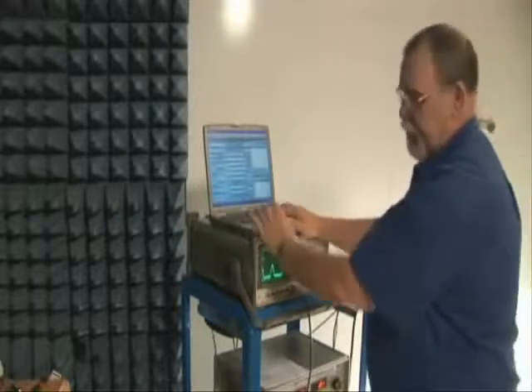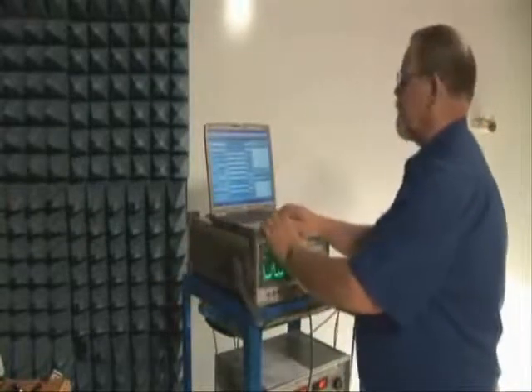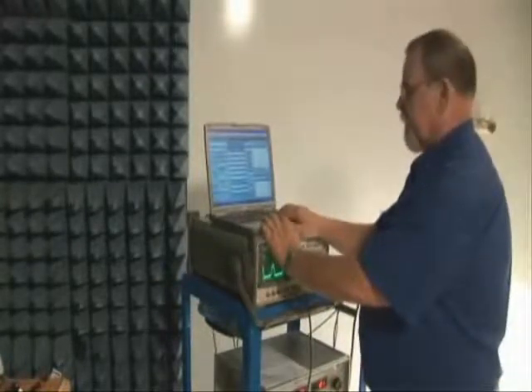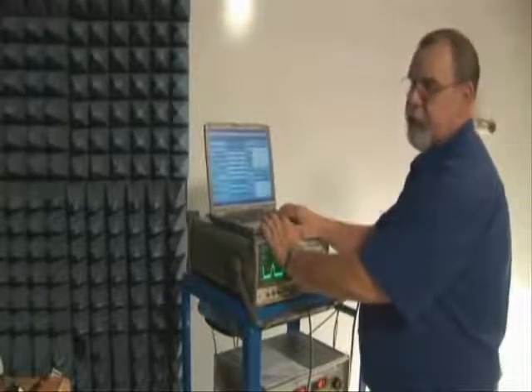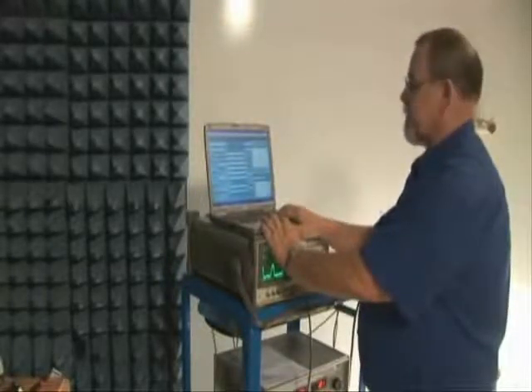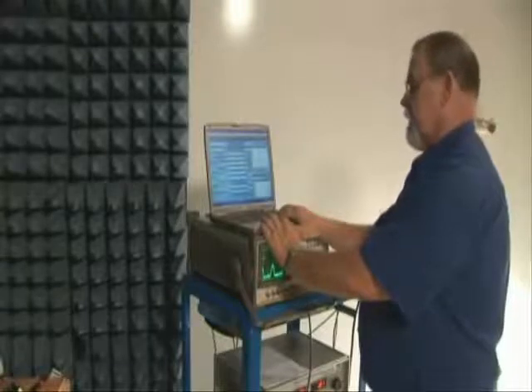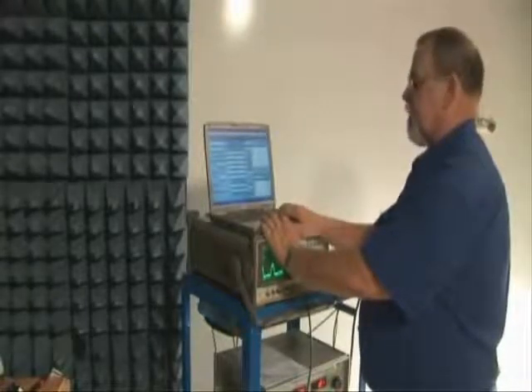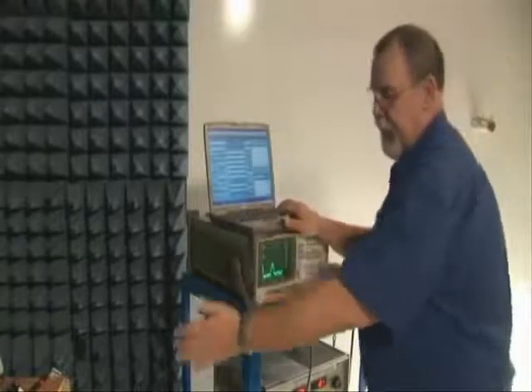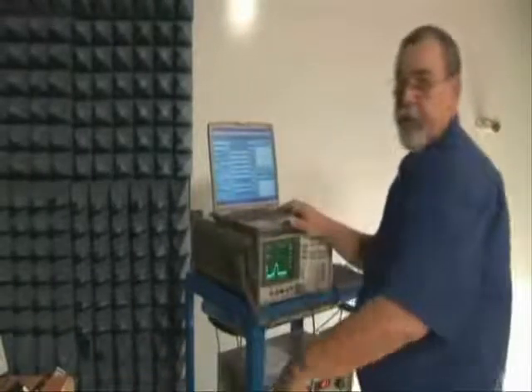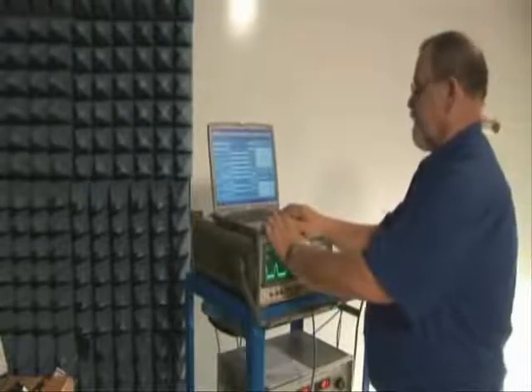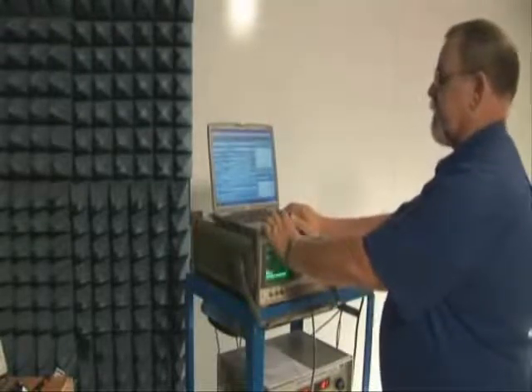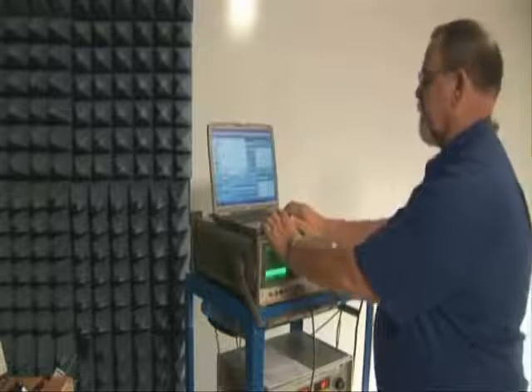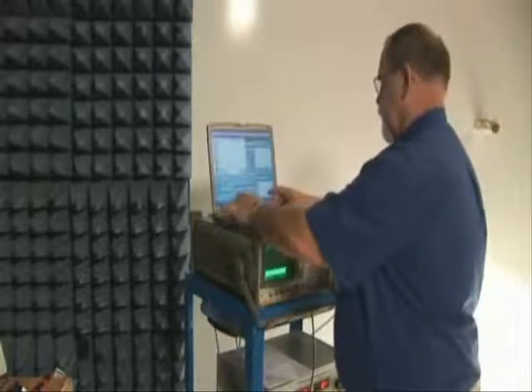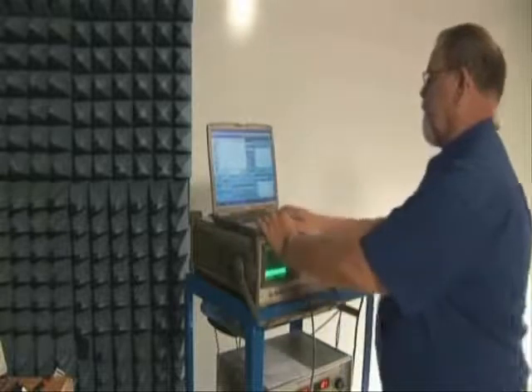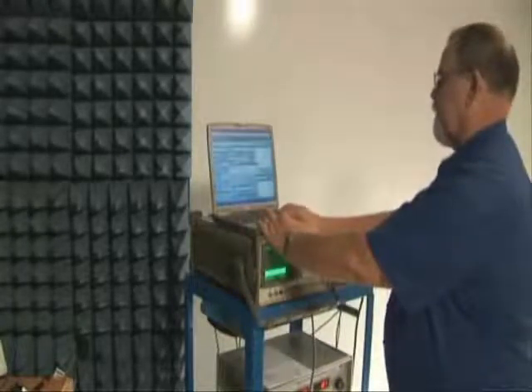We select our current probe that we're using, and the current probe we chose was number 615. We use this file naming convention so we can call up files from our calibration system to know the correction factors. This list selects our equipment in use. For instance, cable number 485 is the one that comes from the current probe to our analyzer. So now the system knows to look up those correction and conversion factors when we start running the software. We select a file name. We're going to call it Cal101 for simplicity, and execute the software to run.